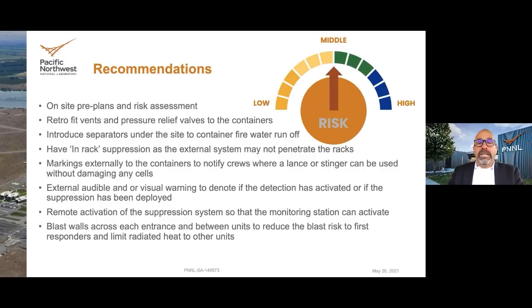Introduce separators underneath the site to contain water fire runoff. I am not sure that you could contain 59 hours of those kinds of flows. Have in-rack fire suppression, as an external system may not penetrate the racks. We are starting to see some manufacturers put water suppression and other agents inside the actual module, which has some promising benefits moving forward.